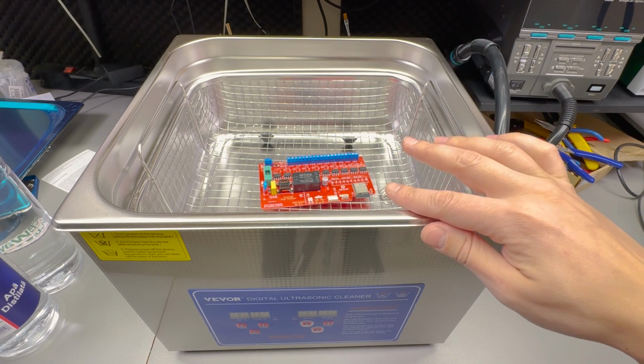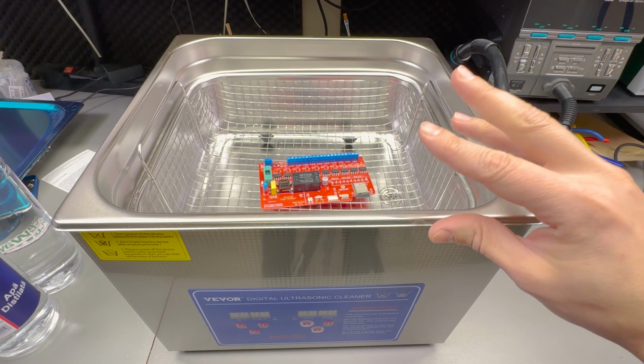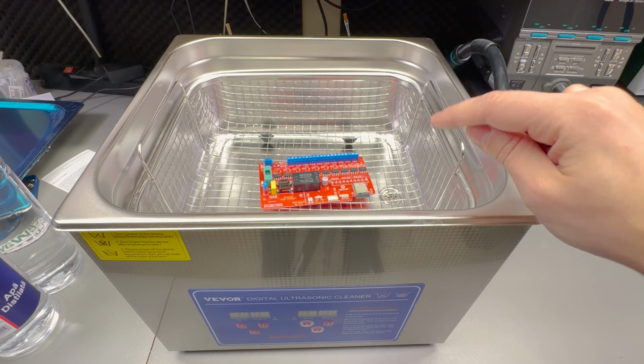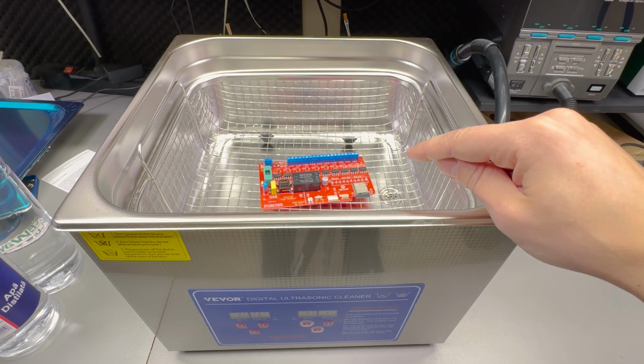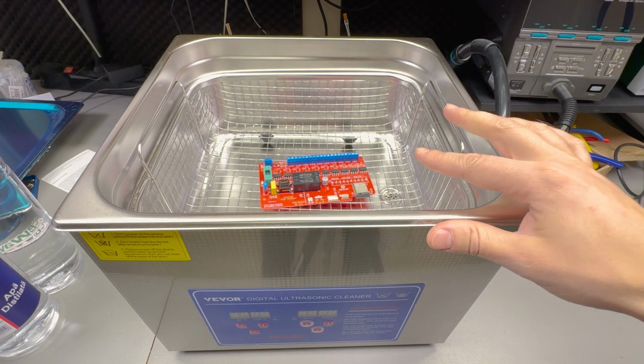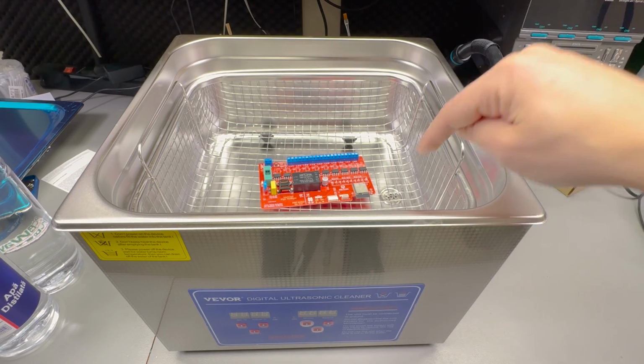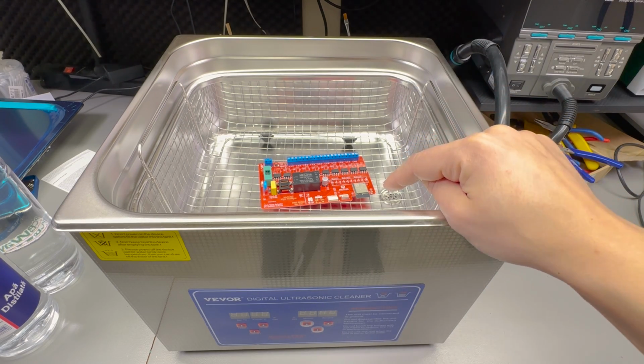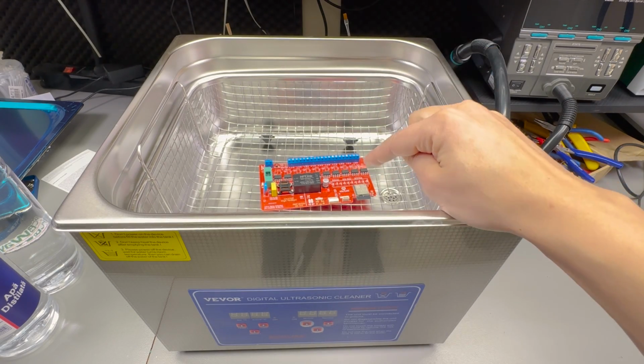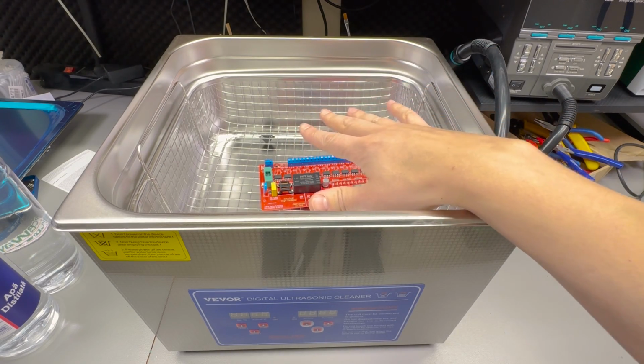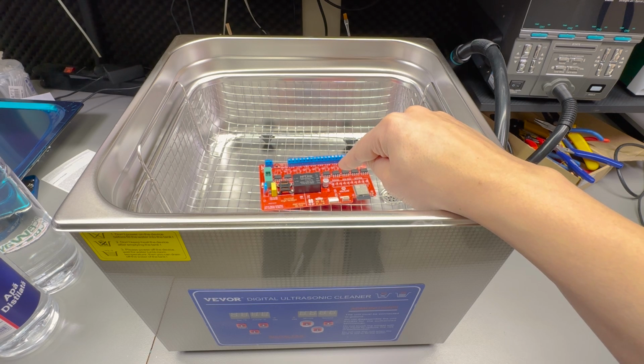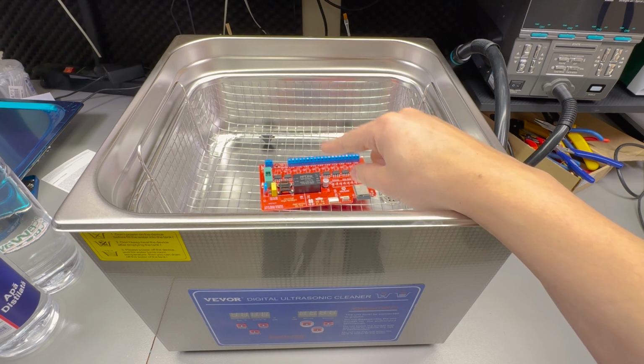Ultrasonic cleaners will have an integrated heater, and they will also heat up just by simply running the ultrasonic transducers, which will lead to overheating if there isn't sufficient liquid inside the tub. Having enough liquid in here ensures even heat distribution and prevents the ultrasonic drivers from overheating during the runtime.